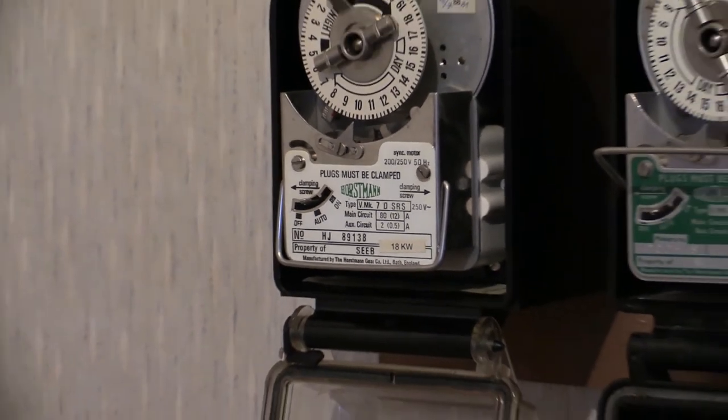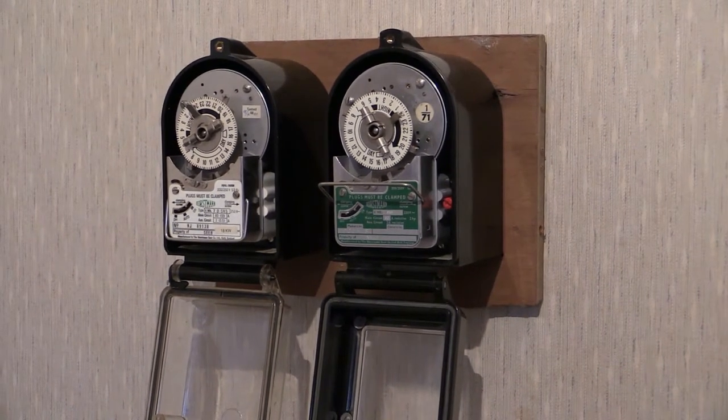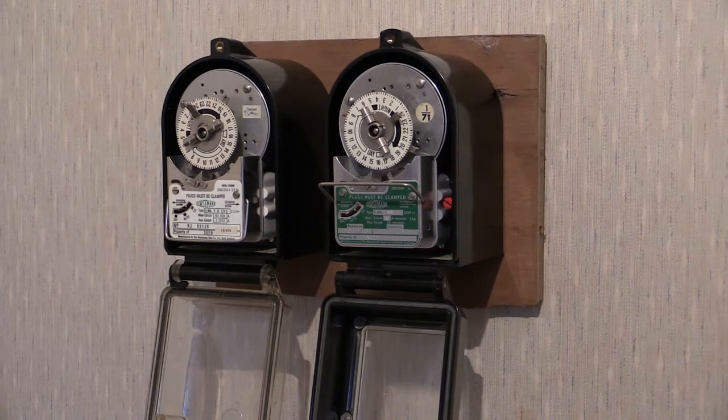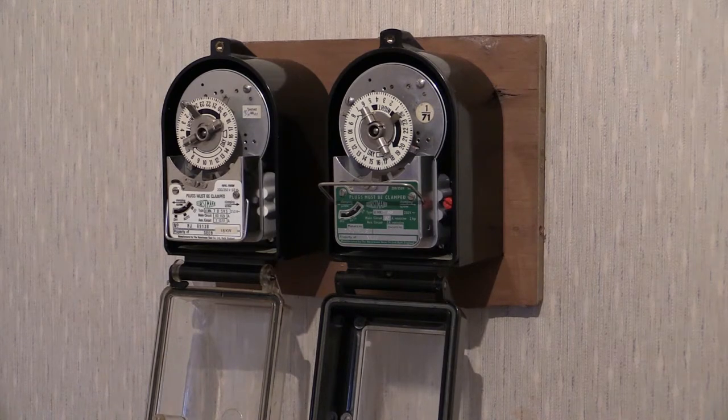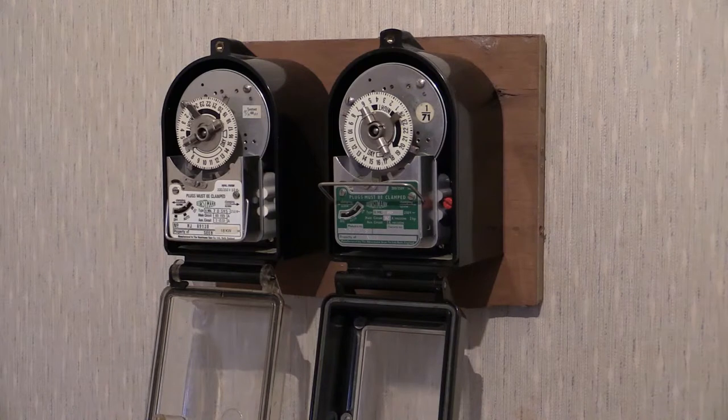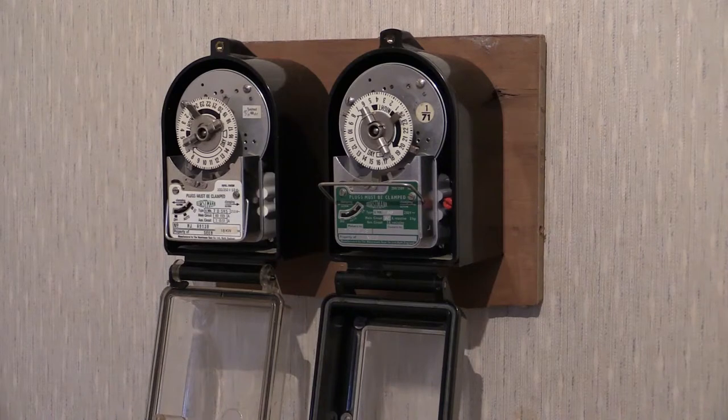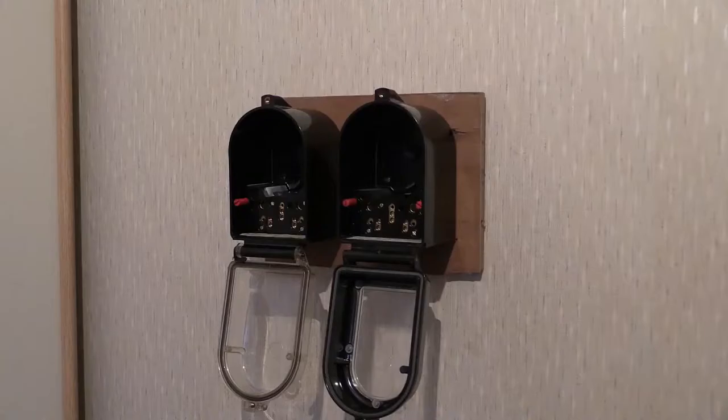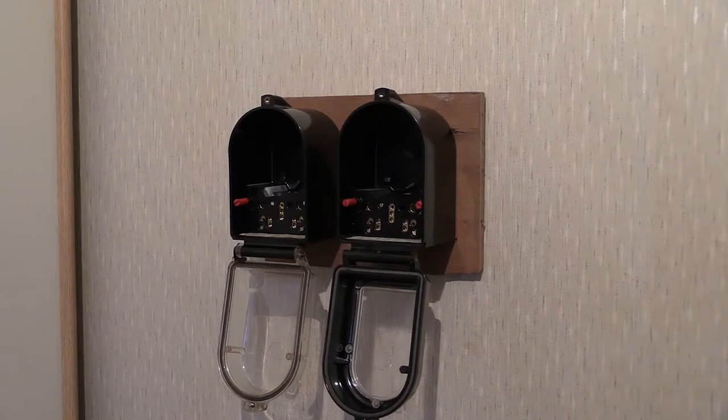With these time switches, you may have to make sure that they are in the off position before you pull them, because if there's 80 amps going through that and you pull it out from the base, I'm betting there would be quite a reasonable arc flash come out of that case, and that could be quite blinding and have a bit of a loud bang to it.